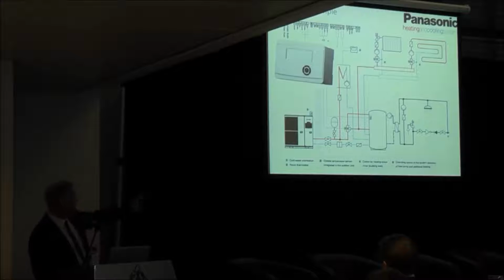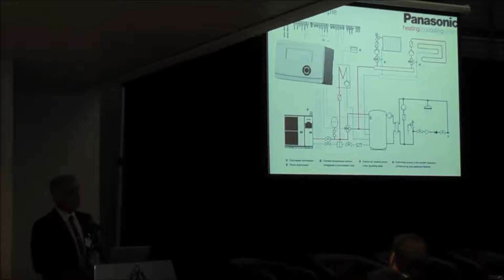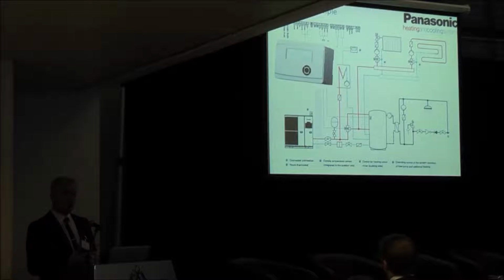We have a product which we call a heat pump manager, which will control the switching between the heat pump and the boiler. We can have true bivalent, where at a certain temperature the heat pump shuts off and the boiler takes over, or we can have cascade, where the heat pump will always run and the boiler will come in periodically to back up the flow temperatures. This is controlled from a heat pump manager.